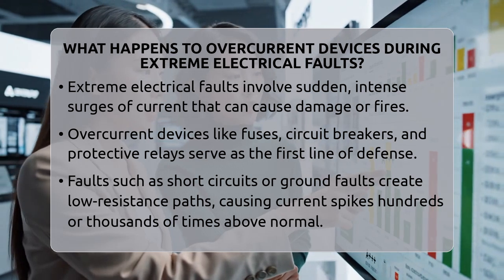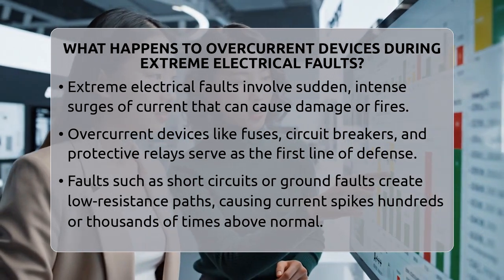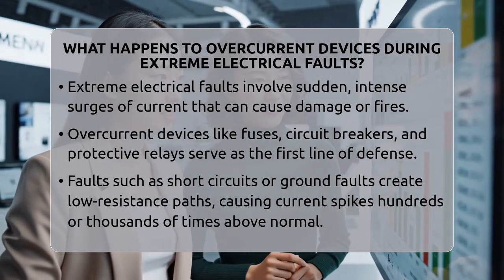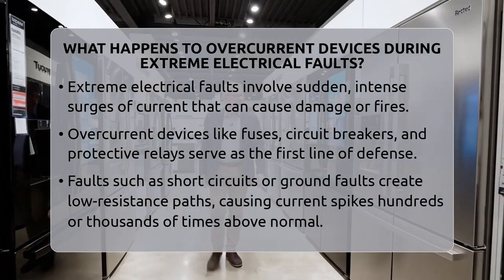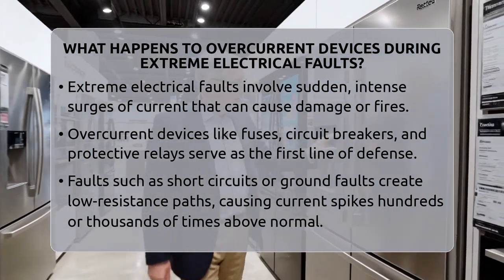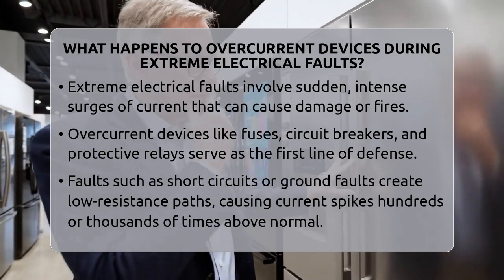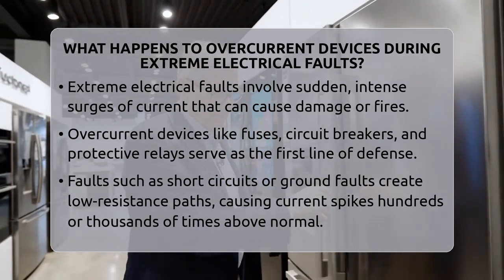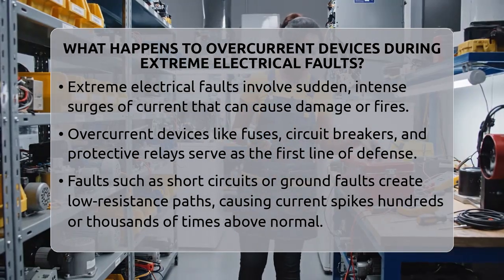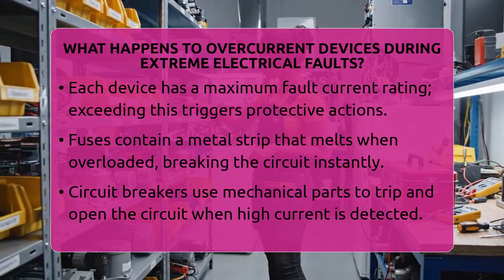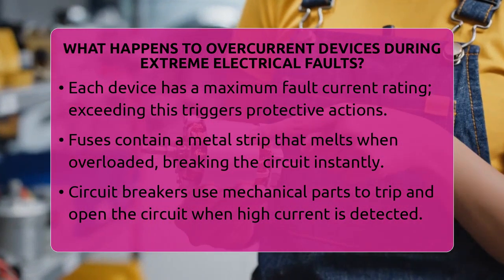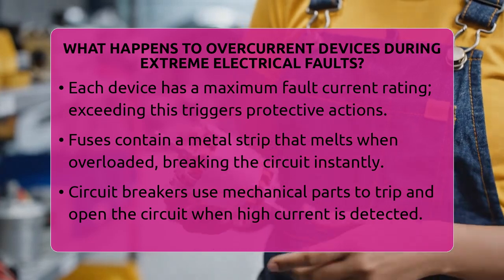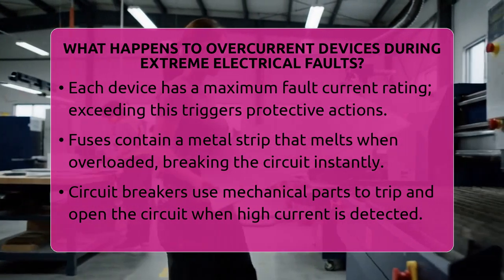When a fault occurs, like a short circuit or ground fault, the current can spike hundreds or even thousands of times above normal levels. These faults happen when wires touch or when equipment fails, creating a low-resistance path for the current. Overcurrent devices are rated for a maximum fault current they can handle safely. If the current exceeds this limit, they need to act fast to prevent damage.